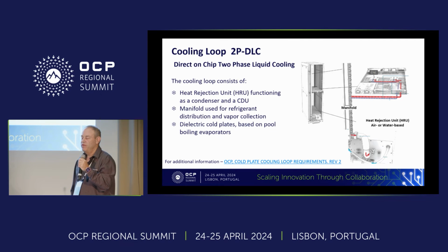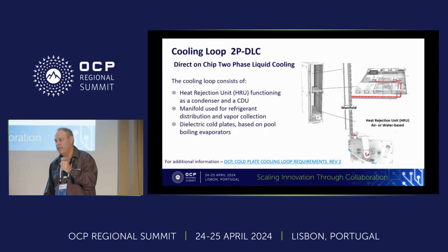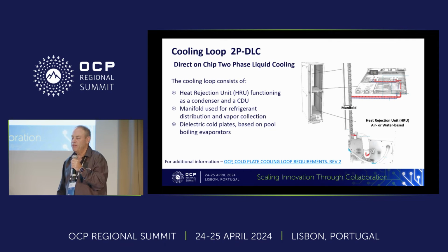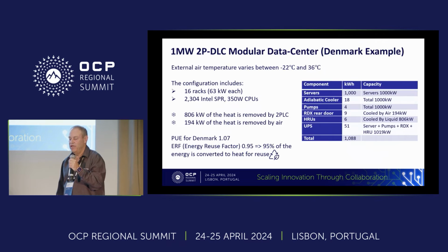All tubes, every server is connected by 2 tubes to that manifold, and the manifold is connected on the bottom of the rack to a CDU or HRU, a heat rejection unit, that removes the heat from the vapor, turning it back to liquid and pumping it back into the manifold into the server. Very simple loop, and just as it looks.